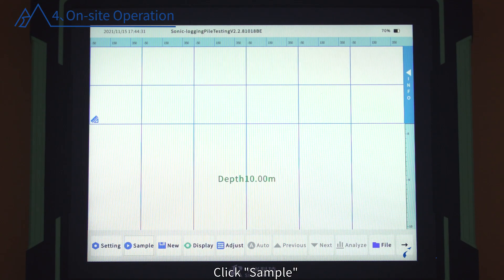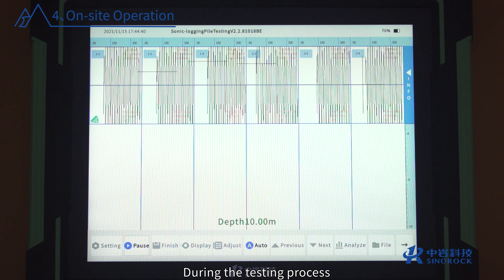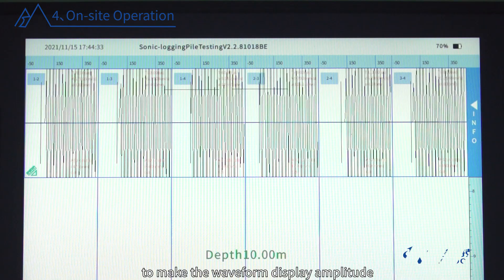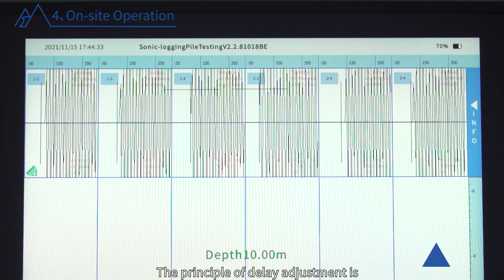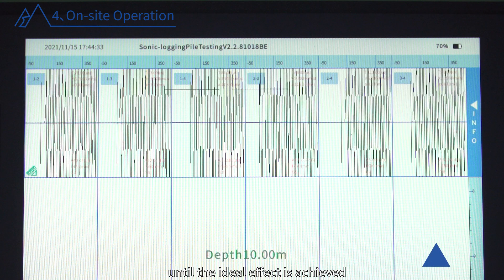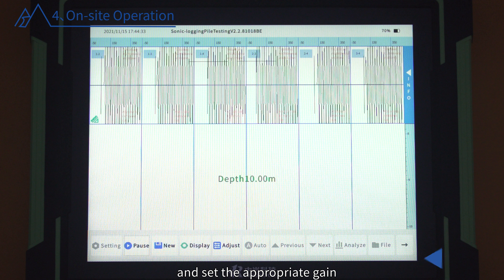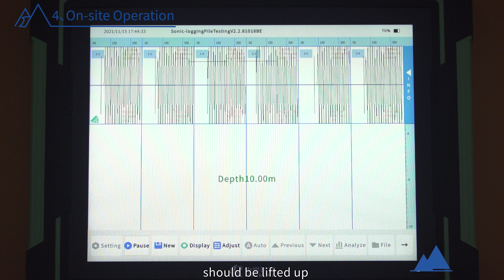Gain and Delay Adjustment: Click Sample and adjust the gain and delay according to the size of the collected waveform and the position of the first wave. During testing, adjustments can also be made by clicking plus and minus in Auto. The principle of gain adjustment is to make the waveform display amplitude fill the display area as much as possible without causing clipping. The principle of delay adjustment is to make the starting position of the signal within the range of one-third to one-half of the abscissa. You can also choose automatic adjustment; the instrument will automatically search for the first wave and set the appropriate gain and delay. If the ideal waveform signal cannot be obtained, after eliminating instrument and sensor faults, lift the transducer to a point without defects to observe whether the signal can be adjusted ideally.